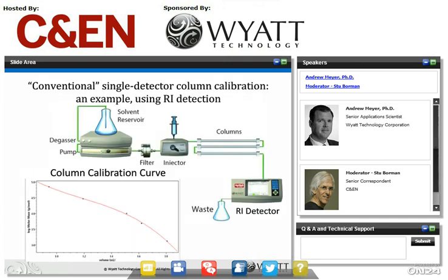In my travels across North America, much to my surprise, I still very often meet with polymer chemists who are using a single detector calibration-based method for HPLC work. Here we see a diagram of a basic GPC system using a refractive index detector after the chromatography column. After injecting a series of standards, like known polystyrenes, we can construct a calibration curve using the apex of each standard peak eluting, resulting in something like this polynomial fit you see on the bottom left of the slide. This approach has been used for decades.